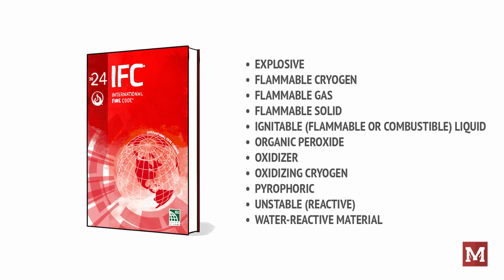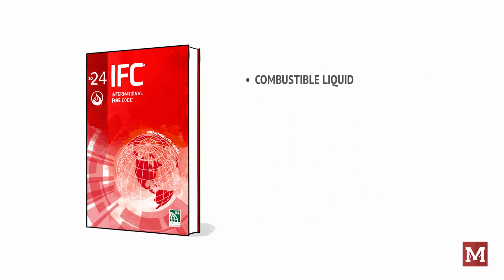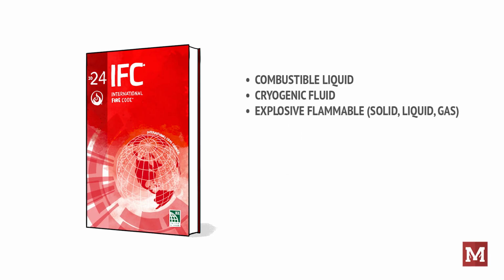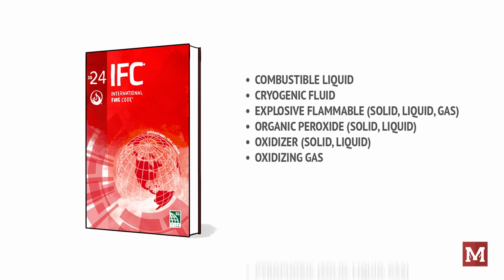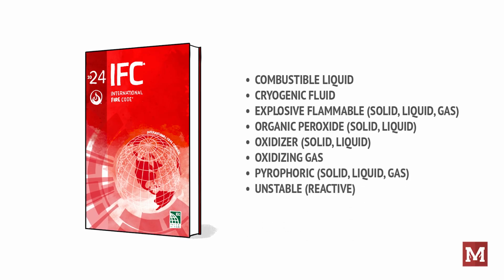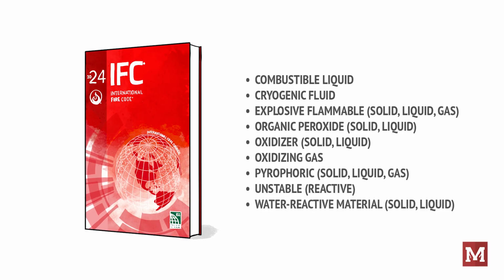And looking at the IFC definition, a physical hazard is a chemical for which there is evidence that it is a combustible liquid, cryogenic fluid, explosive, flammable solid, liquid, or gas, organic peroxide, oxidizer, oxidizing gas, pyrophoric, unstable reactive material, or a water reactive material. While slightly different phrasing, the core classifications are consistent between these two codes.